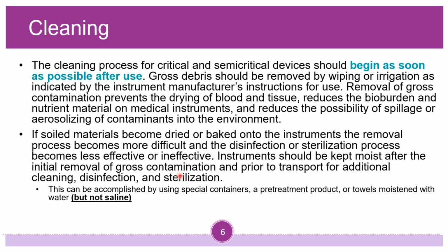The cleaning process for critical and semi-critical devices should begin as soon as possible after use. Gross debris should be removed by wiping or irrigation as indicated by the instrument manufacturer's instructions for use, the IFUs. Removal of gross contamination prevents the drying of blood and tissue, reduces the bioburden and nutrient material on medical instruments, and reduces the possibility of spillage or aerosolizing of contaminants into the environment. Now, this is extremely important.